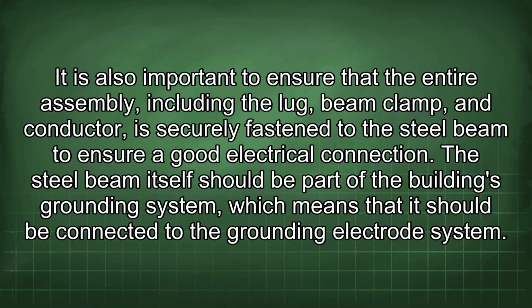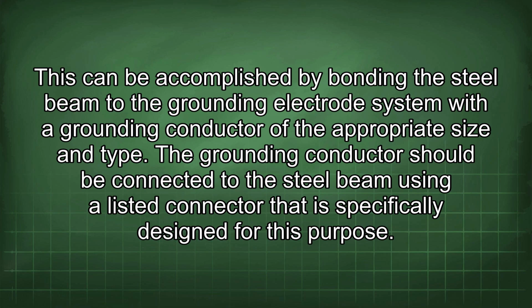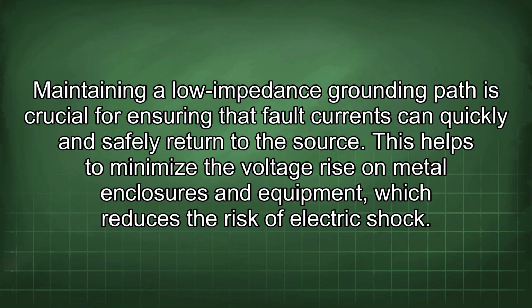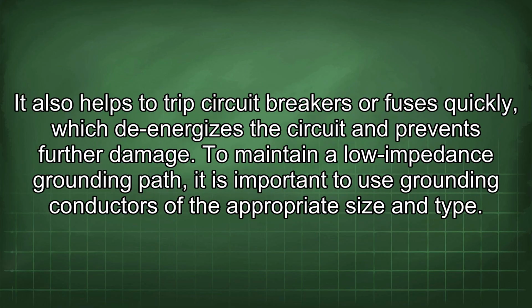The steel beam itself should be part of the building's grounding system, which means that it should be connected to the grounding electrode system. This can be accomplished by bonding the steel beam to the grounding electrode system with a grounding conductor of the appropriate size and type. The grounding conductor should be connected to the steel beam using a listed connector that is specifically designed for this purpose. Maintaining a low impedance grounding path is crucial for ensuring that fault currents can quickly and safely return to the source. This helps to minimize the voltage rise on metal enclosures and equipment, which reduces the risk of electric shock. It also helps to trip circuit breakers or fuses quickly, which de-energizes the circuit and prevents further damage.